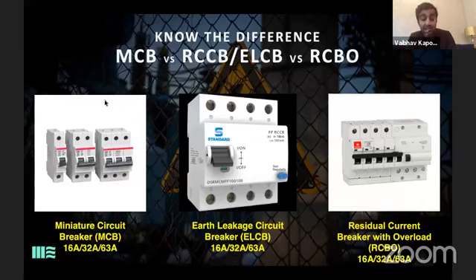Now comes the RCBO. RCBO is a combination of MCB and ELCB. It does all the functions - overload, short circuit, and earth fault leakage. So you can either use an RCBO separately since it does all the functions, or use MCB and ELCB separately, depending on your application. For my live events, I'm using MCB and ELCB both. There's a reason behind it, which I'll talk about.